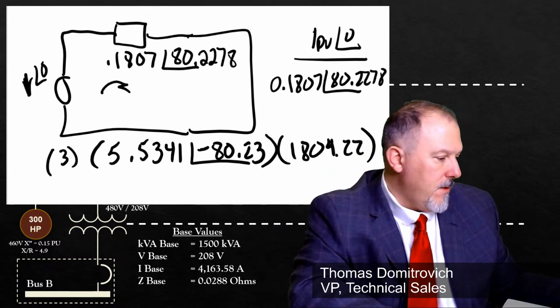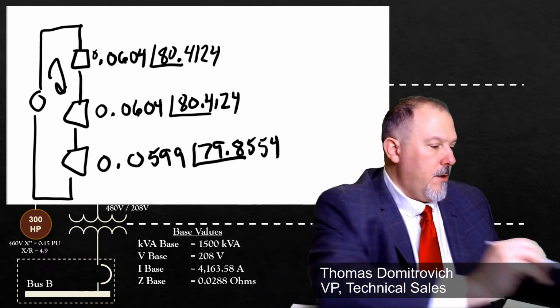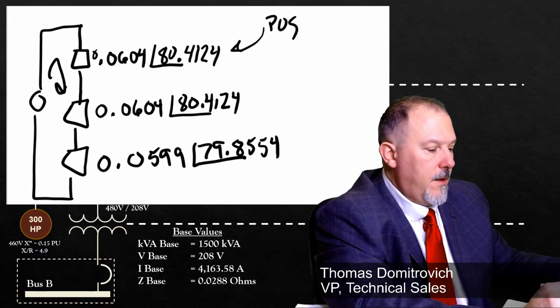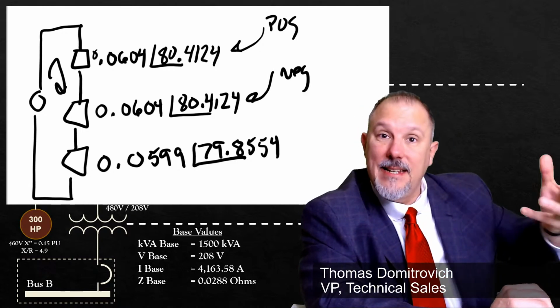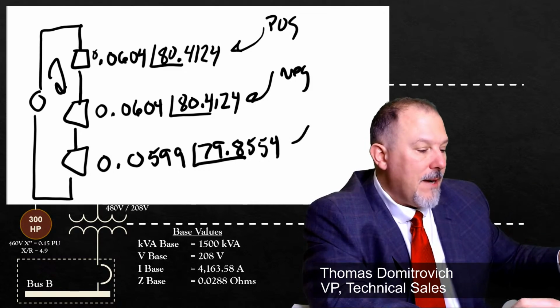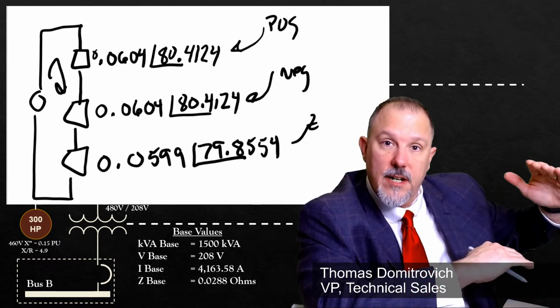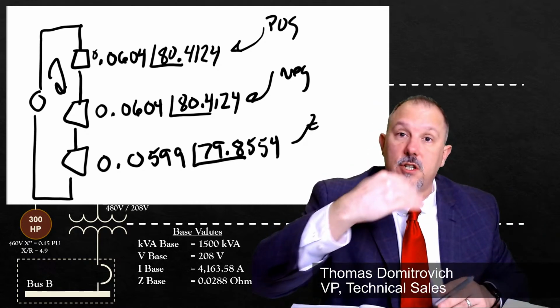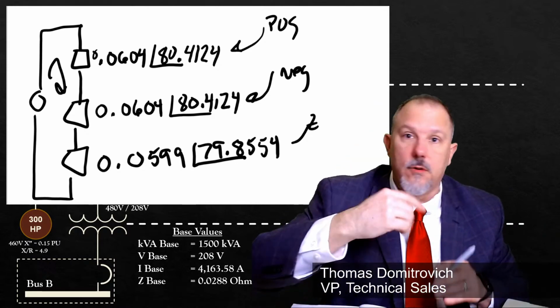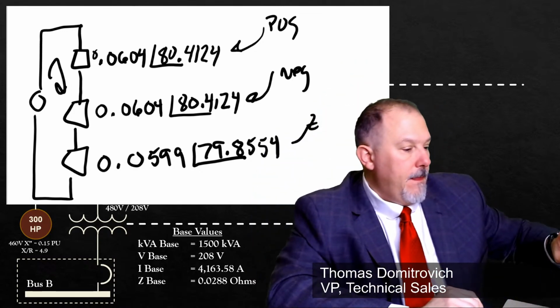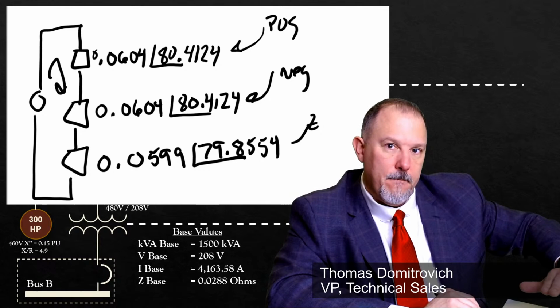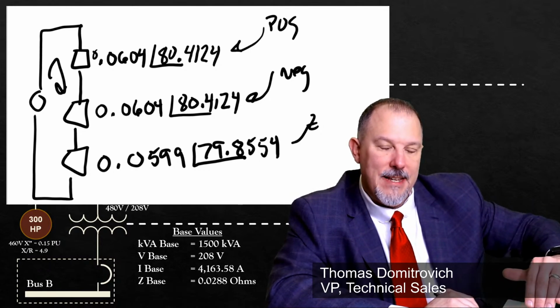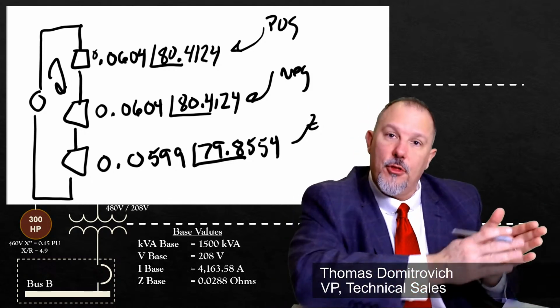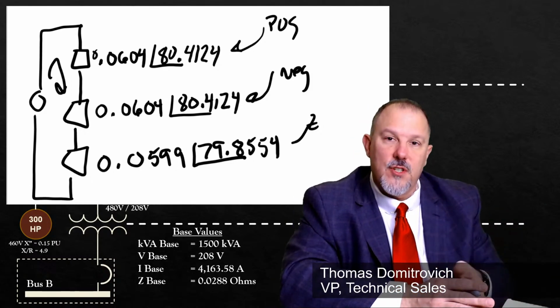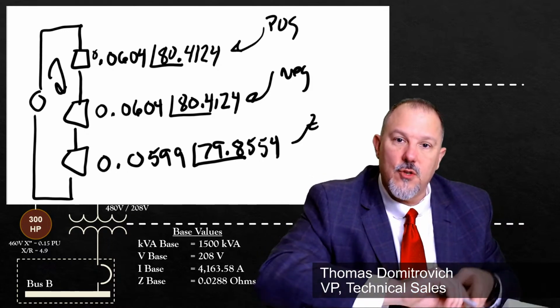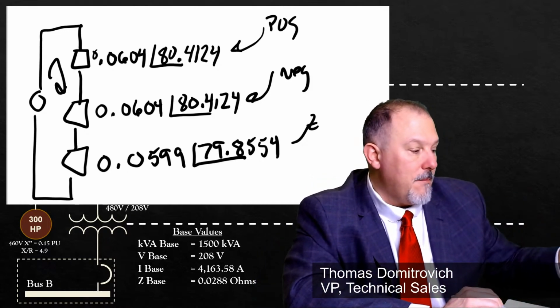If I go up, right? So this was my positive sequence. This is my negative sequence. I basically doubled it because both of those are the same. But my zero sequence isn't the whole circuit. I only include the portion of the circuit to the secondary of the transformer and the transformer. I don't include the impedances up above. So I'm adding all of these together to get a ground fault current. And then I'm going to multiply that by 3 because all 3 of those zero sequence currents are in phase with each other.